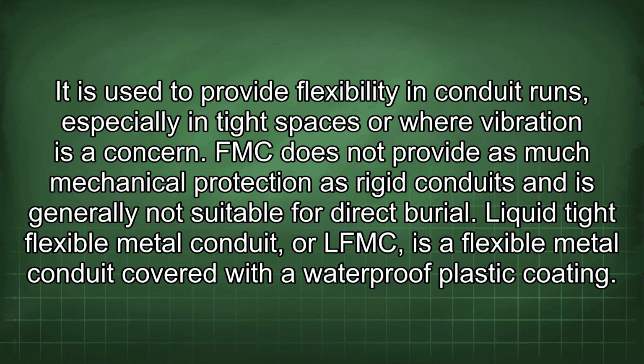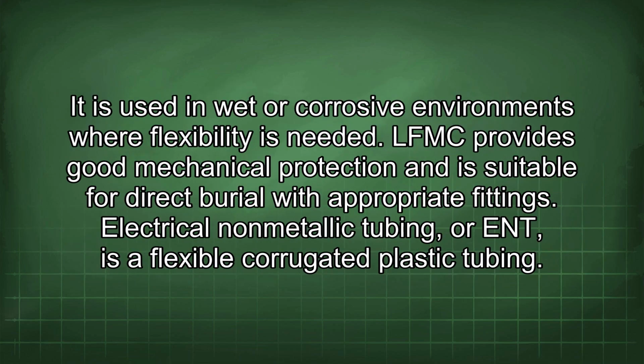Liquid-tight flexible metal conduit, or LFMC, is a flexible metal conduit covered with a waterproof plastic coating. It is used in wet or corrosive environments where flexibility is needed. LFMC provides good mechanical protection and is suitable for direct burial with appropriate fittings.